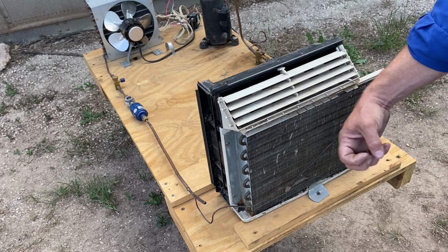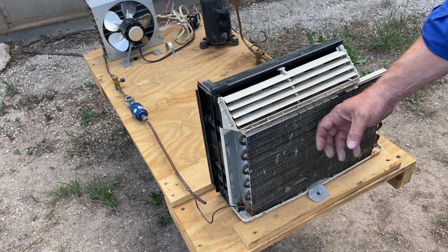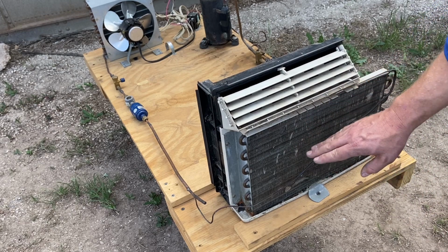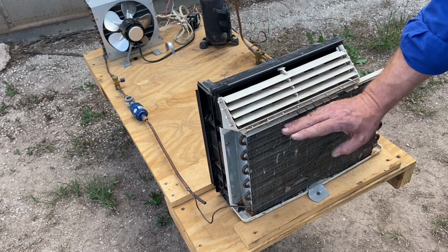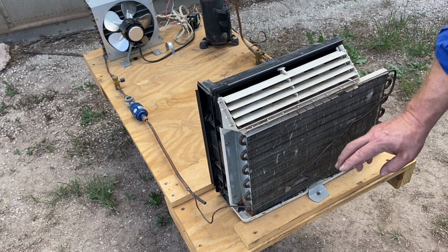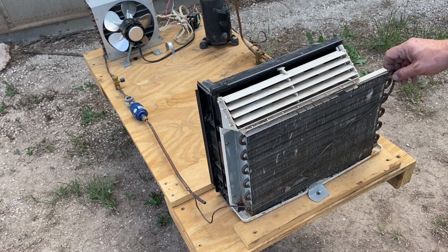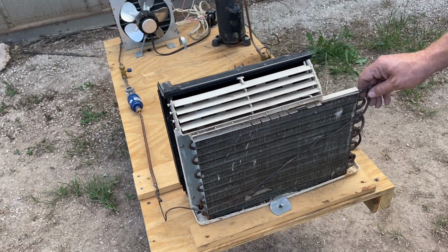In other words, absorbing heat away from the air. It's cooling the air off. The heat goes to the refrigerant to make the refrigerant boil. The refrigerant boiling is absorbing the heat. Now after we boil it all from a liquid to a vapor, the very last little bit of this coil superheats above saturation, but it's still low temperature.